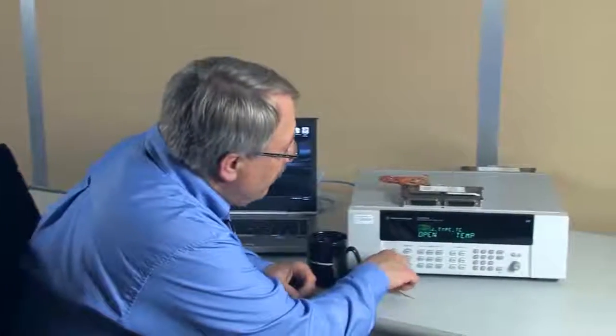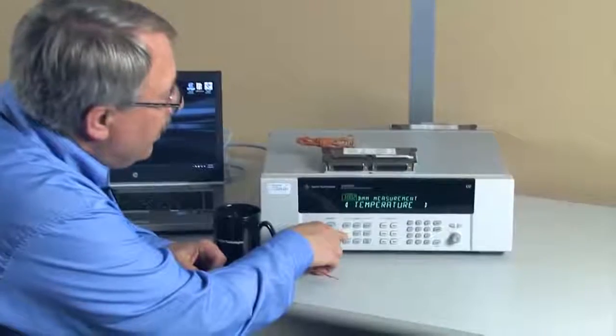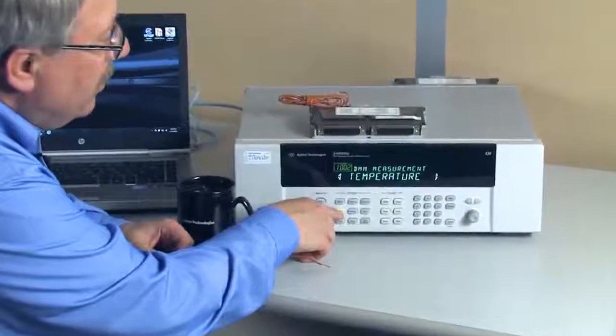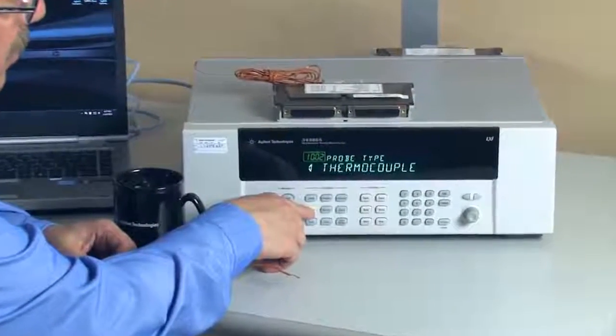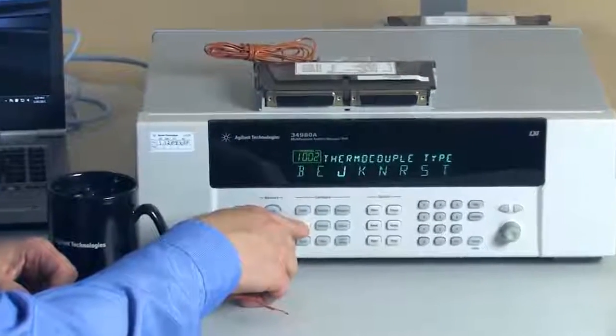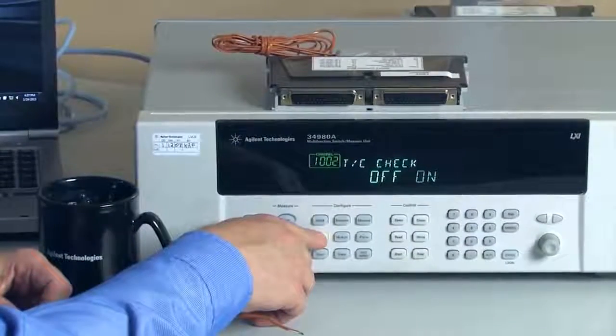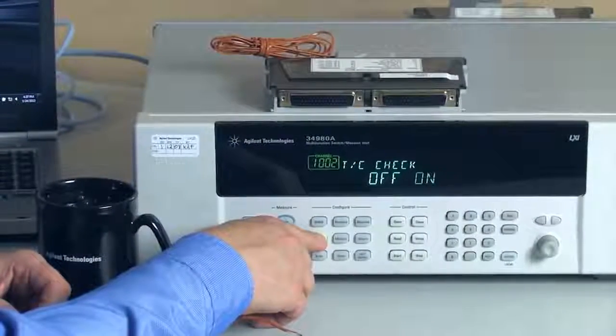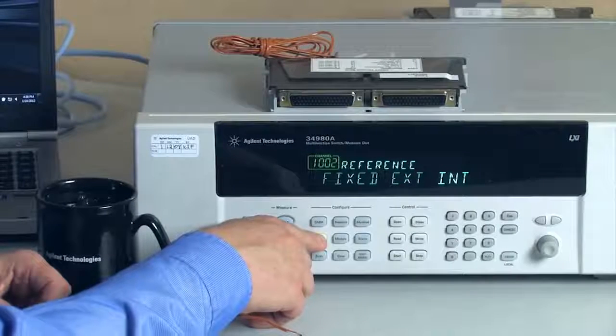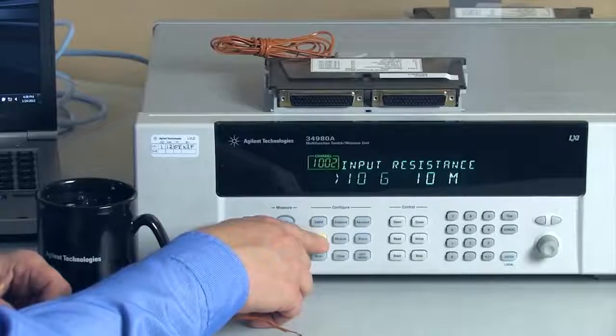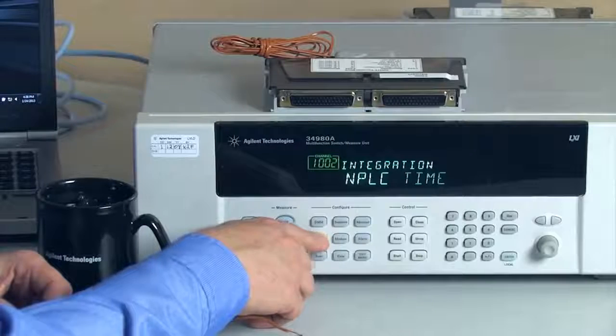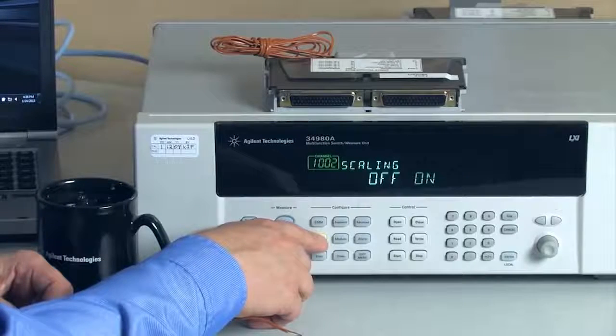To control the 34980 from the front panel, we do two things. We simply configure a channel, and then we measure the channel. First, we hit configure for the channel. We'll select temperature, thermocouple, J-type, thermocouple check off. We're going to use an internal temperature reference, and for the rest we will select the defaults.